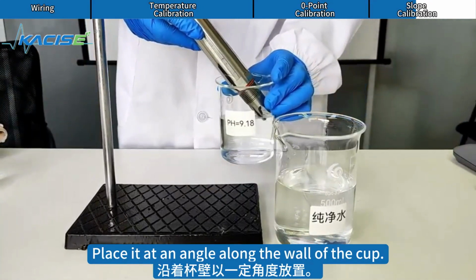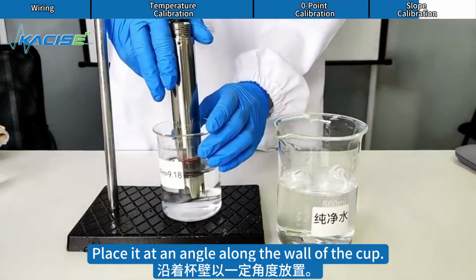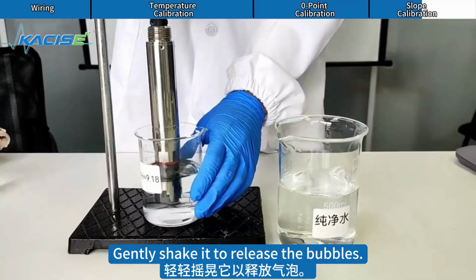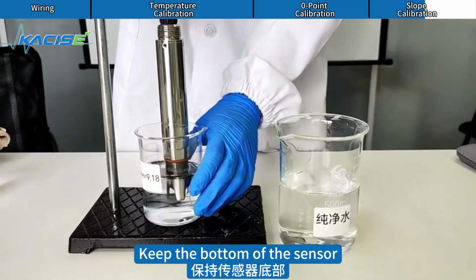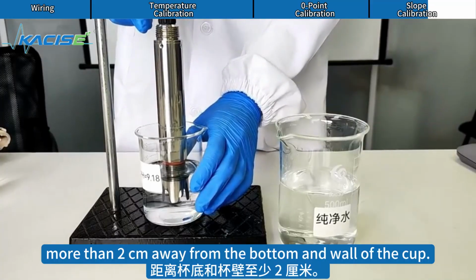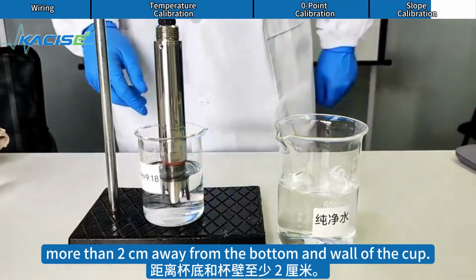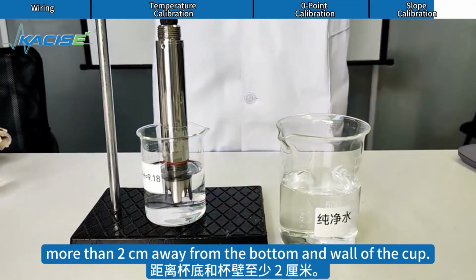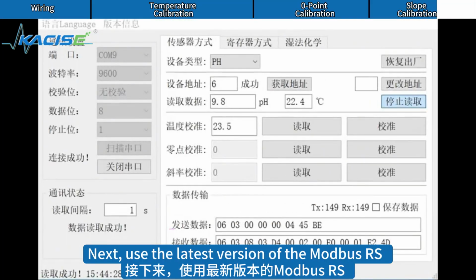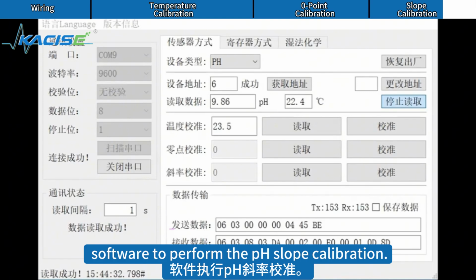Place it at an angle along the wall of the cup. Gently shake it to release the bubbles. Keep the bottom of the sensor more than 2 centimeters away from the bottom and wall of the cup. Next, use the latest version of the Modbus RS485 software to perform the pH slope calibration.